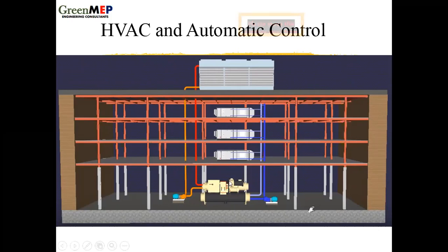Okay. There's a refrigeration cycle going, and to cool down the refrigerant, you know that if you go close to your refrigerator at home, particularly the backside, you will feel it's very warm out there, because that is where the hot refrigerant in the refrigeration cycle is cooled down at the condenser. Here, the condenser we're talking about has a water cooling system. This water is called condenser water. The condenser water is supplied by the cooling tower, right? Condenser water comes in. You need motors again to circulate it. It goes through, absorbs heat from the refrigerant, and goes back to the cooling tower. The cooling tower uses large fans to cool this water down and supplies condenser water at a constant temperature, just like this supplies chilled water at constant temperature.